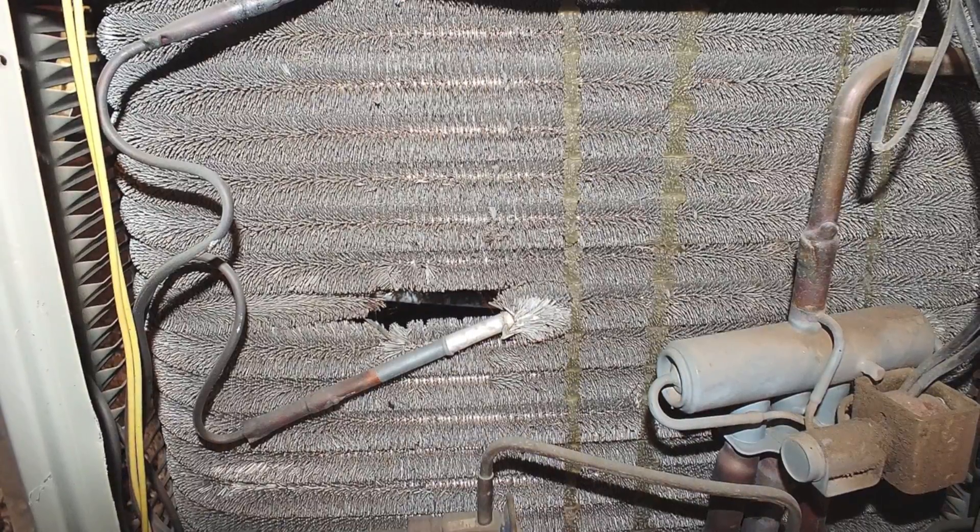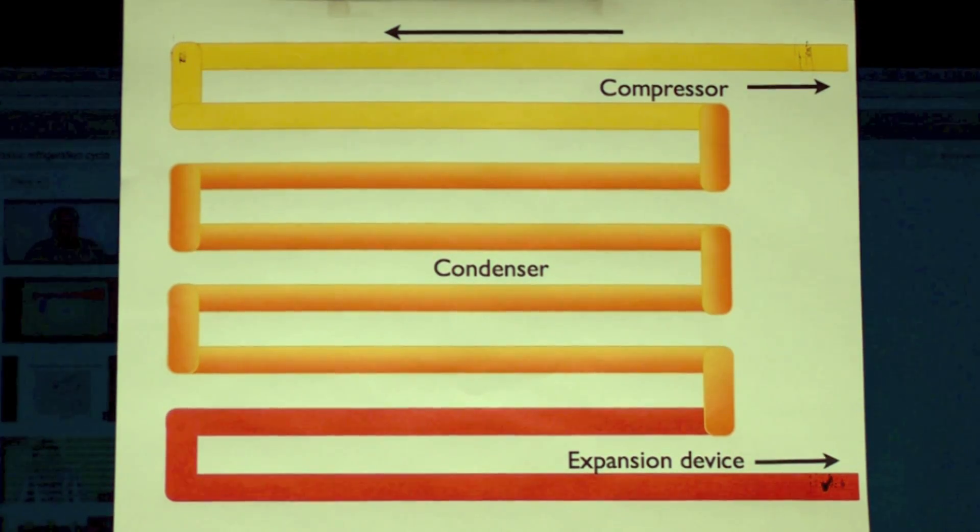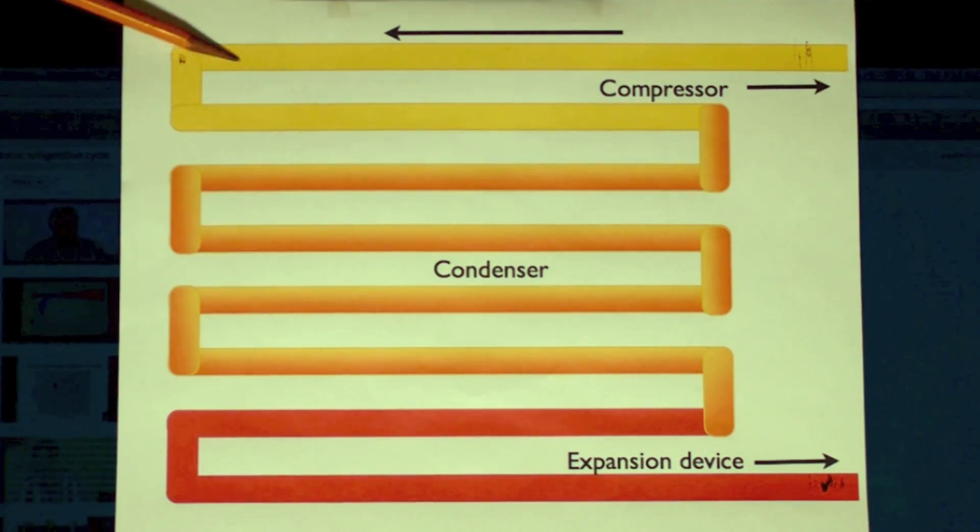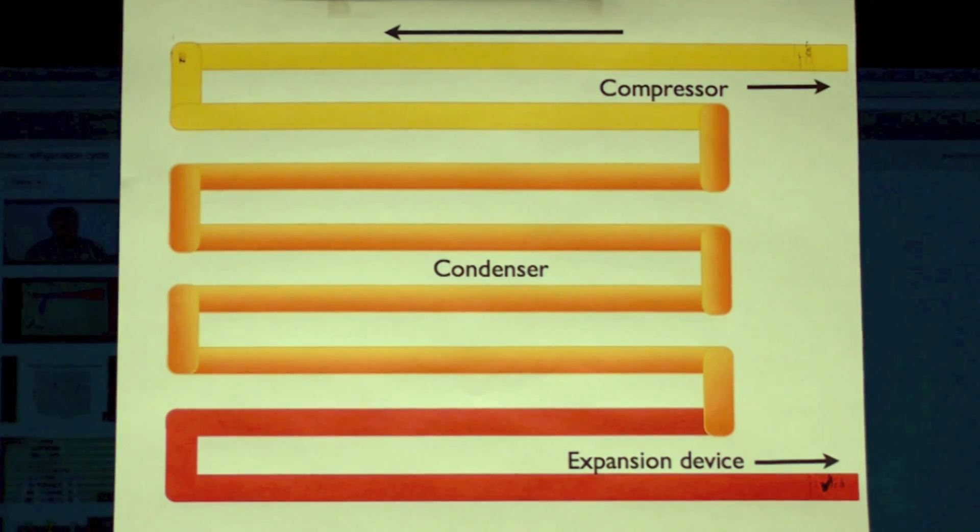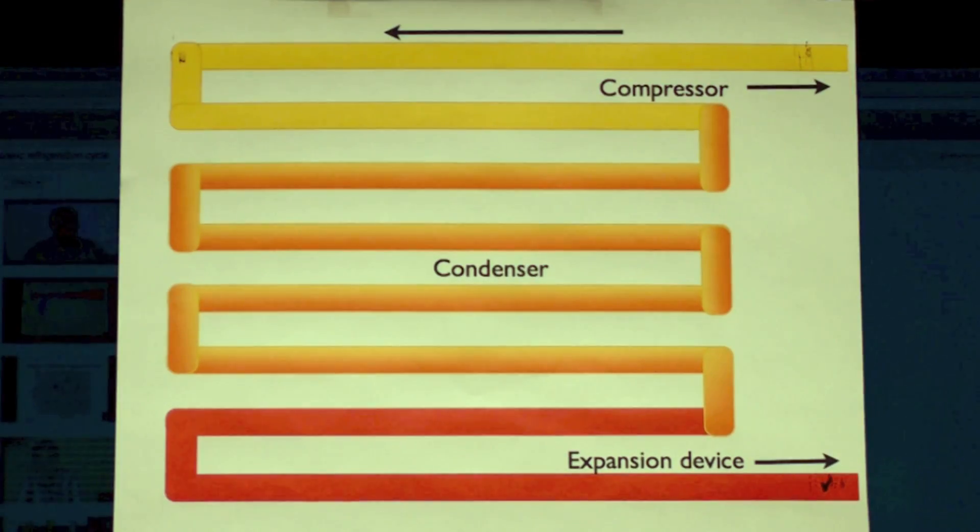Okay, the condenser's job. The condenser has three functions. The first function is to desuperheat. We're coming from the compressor here, going over like this. The yellow is the hot gas desuperheating down. This is an air-cooled condenser, that can be water-cooled. It runs between 20 and 30 degrees above the outside ambient.